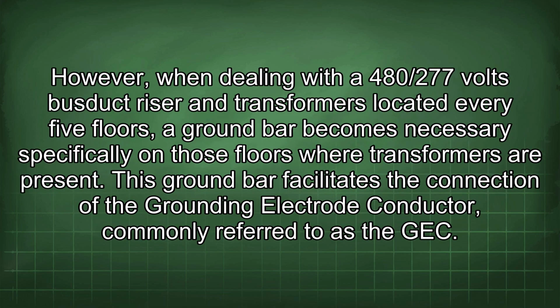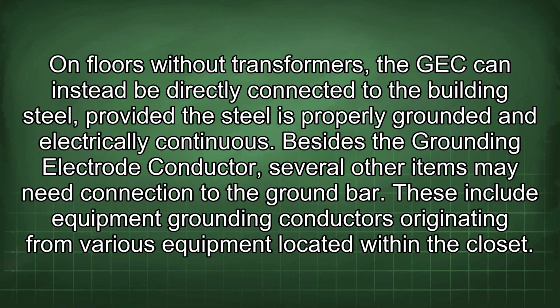However, when dealing with a 480/277 volts bus-duct riser and transformers located every 5 floors, a ground bar becomes necessary specifically on those floors where transformers are present. This ground bar facilitates the connection of the grounding electrode conductor, commonly referred to as the GEC. On floors without transformers, the GEC can instead be directly connected to the building steel, provided the steel is properly grounded and electrically continuous.